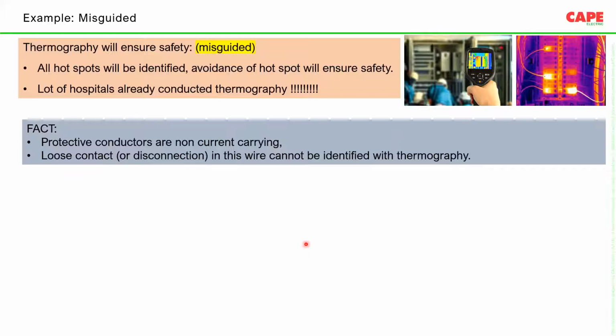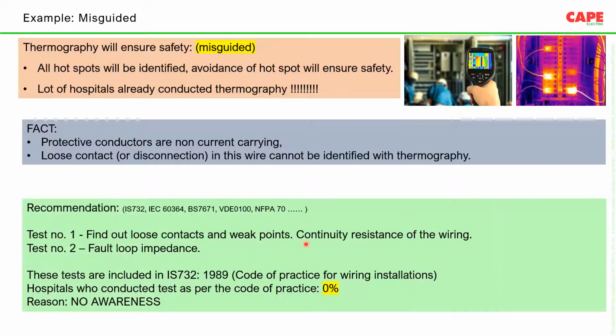Why do people recommend thermography? Because they are not aware of what testing is exactly recommended in the standard. IS 732 in 1989, 31 years back, recommended basic testing measures in an electrical installation, which we don't do. As a result, we don't know what testing is required, but we always go for the high class. Somebody says thermography, and there is a beautiful camera, a beautiful picture. You can always look at the picture and be happy. But unfortunately, this does not give you the desired result.